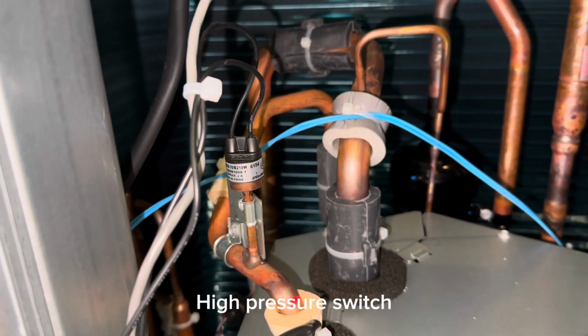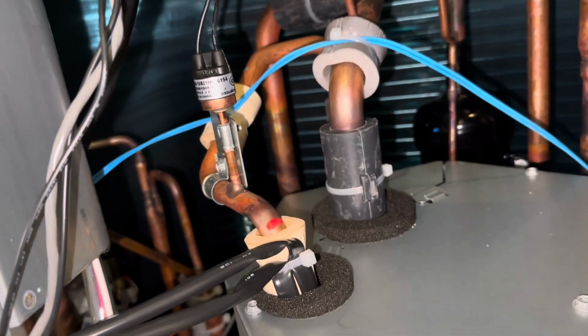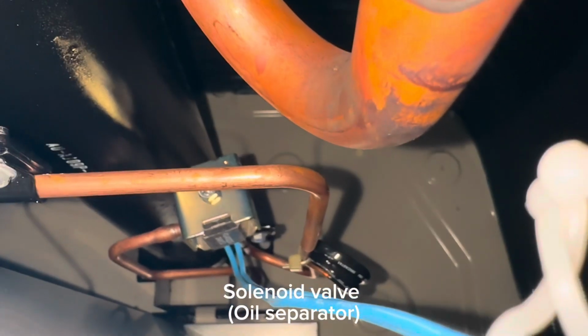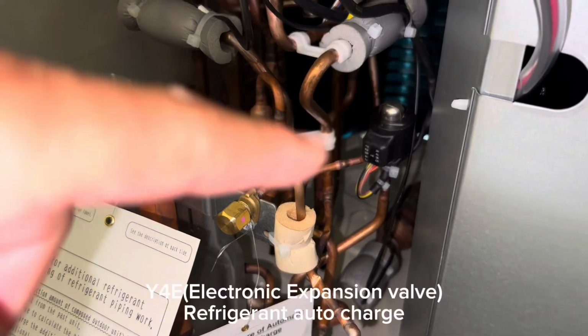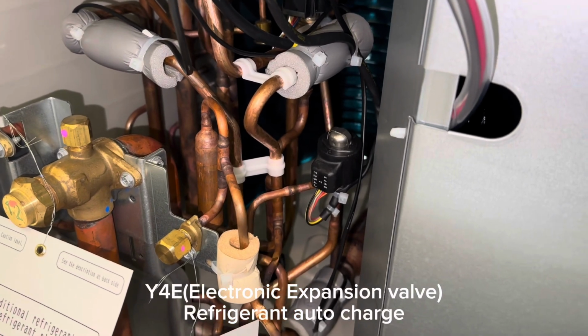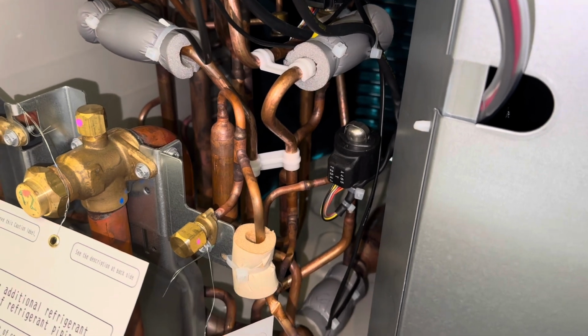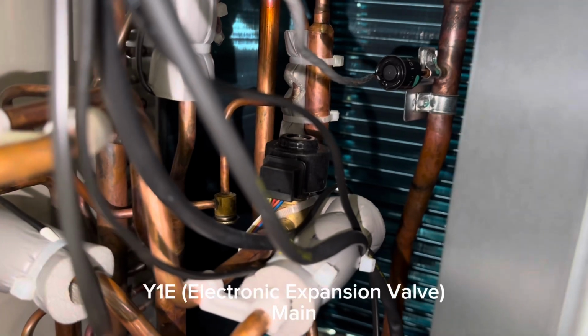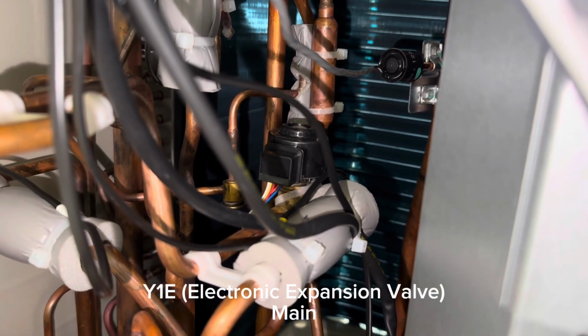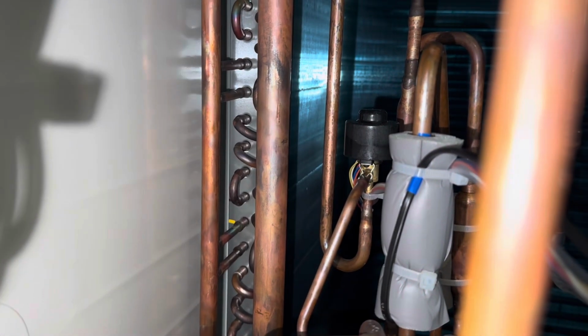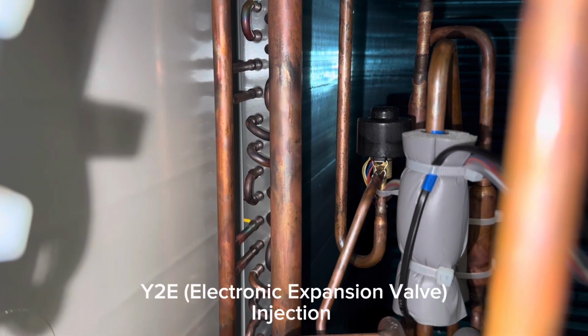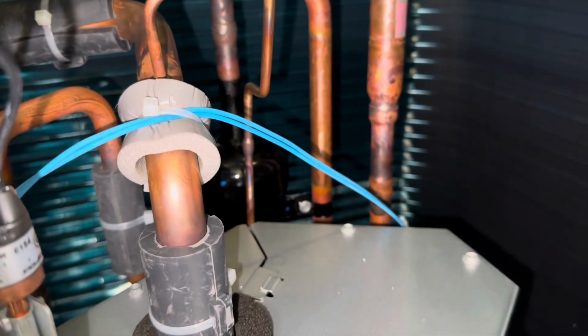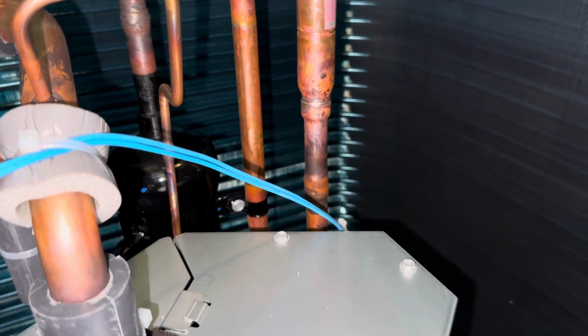Okay, this one on top of the compressor is a high pressure switch. Okay, this is an auto charge Y4E, electronic expansion valve, refrigerant auto charge. The second one on top is the main electronic expansion valve, main Y1E. Another one on top, near the condensing coil, is the injection electronic expansion valve, Y2E. Blue color wire is Y3S solenoid valve, oil separator.